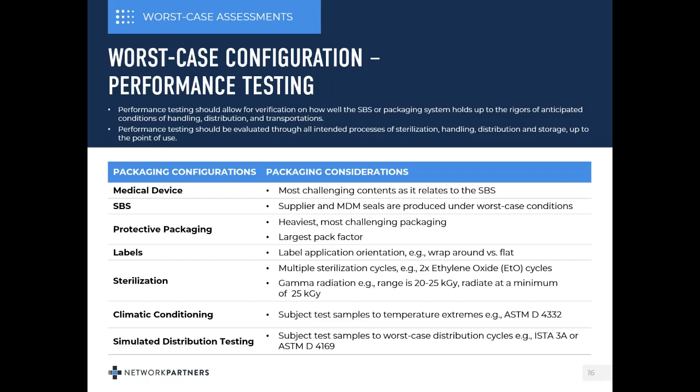Well, the awesome news was we had an FDA audit going on, and somebody brought me into the warehouse, and all these labels were kind of flipping back. They call it the spring back motion because of the material. There wasn't enough real estate to stick, and the adhesive with the corrugated wasn't strong enough. So I had to go back. I revalidated everything with a stronger adhesive. So you always want to keep that in the back of your head too.